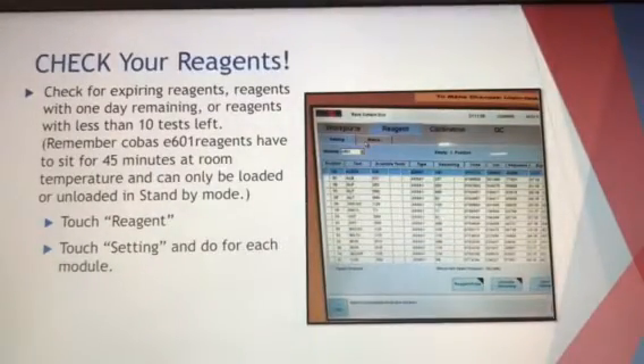Also, the 601 reagents, make sure you check them now and go ahead and get them out, because they do take 45 minutes. They have to sit at room temp for 45 minutes before they can be put on. So how you can check your reagents is, you can see in that first picture there, you'll be at your main home screen. You can go ahead and click on reagent and make sure that setting is selected, and it'll give you all the reagents that are on the instrument, and it'll tell you how many tests are remaining, and it'll give you the expiration date and how many days are remaining. It's a really good page to check throughout the day. Just keep an eye on it. It's just a good thing to know.